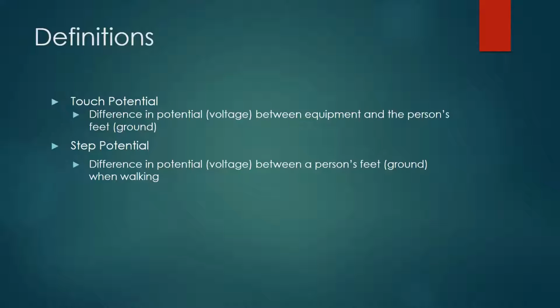Touch potential is going to be the difference in potential between equipment and the person's feet when they're working on it, so when they're touching it. While step potential will be the difference in potential between a person's feet when they're walking. Obviously, we don't want the path of least resistance to be through someone's body because that would not be good for our substation. That would not be safe for our design.